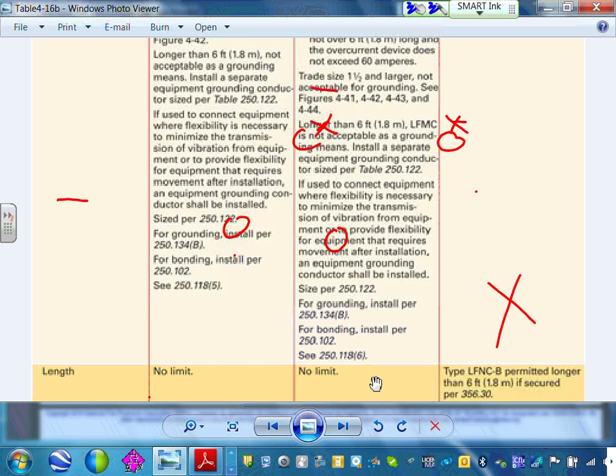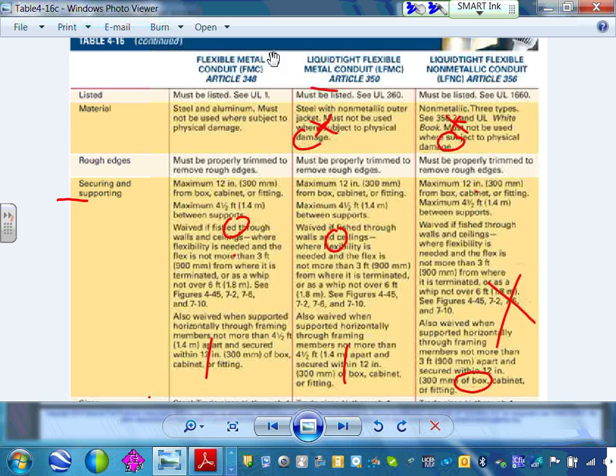Yeah, length. Is there a limitation on the length that you can use? Can I use 100 feet of this? Bring it on. 100 feet of this? Bring it on. But that non-metallic, what's the limitation on the non-metallic? 6 feet. So fixture whip, the limitation of using it. So you can't use it as a wiring method. You just use it as tying to equipment. Okay, so you guys have all this one.